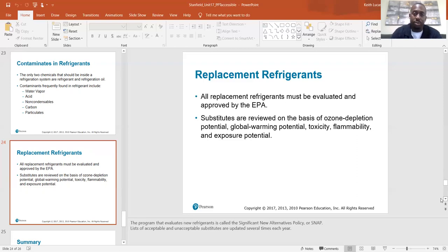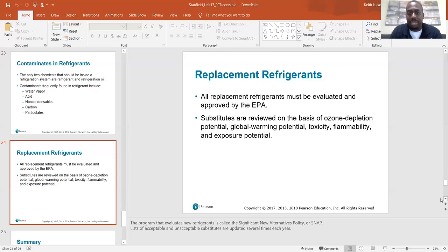Also replace the filter dryer whenever you open a system — you've got to put in a new filter dryer. Replacement refrigerants: all replacement refrigerants must be evaluated and approved by the EPA. Substitutes are reviewed on the basis of ozone depletion potential, global warming potential, toxicity, flammability, and exposure potential. The program that evaluates new refrigerants is called the Significant New Alternatives Policy, or SNAP. Lists of acceptable and unacceptable substitutes are updated several times each year.